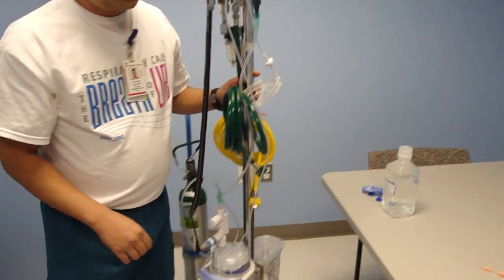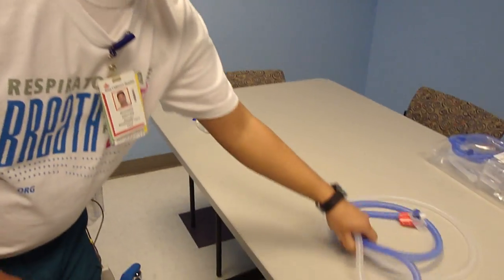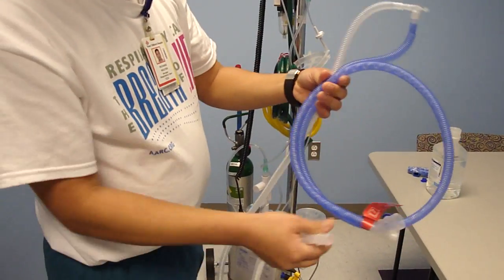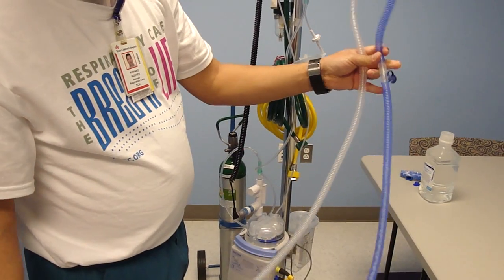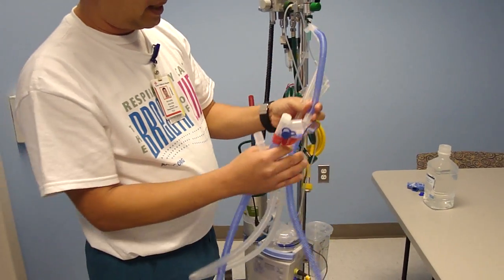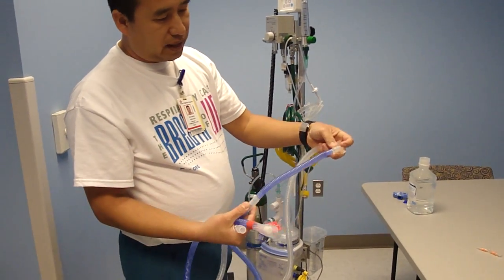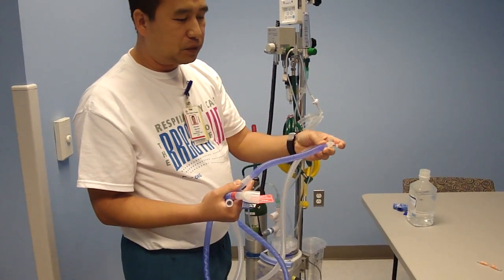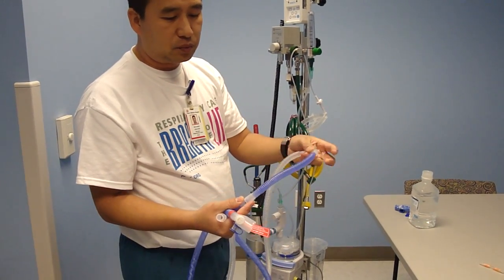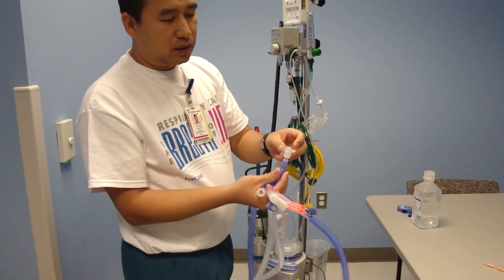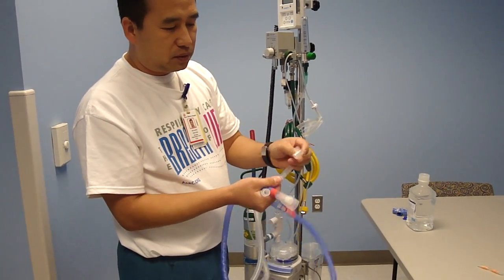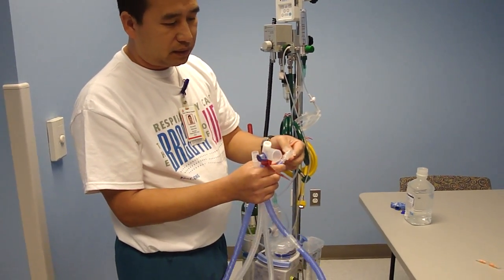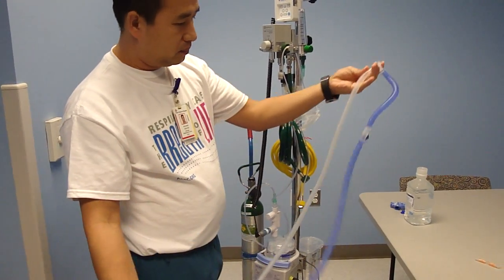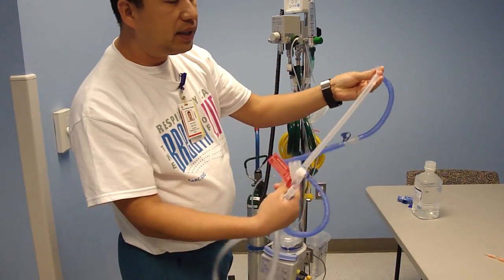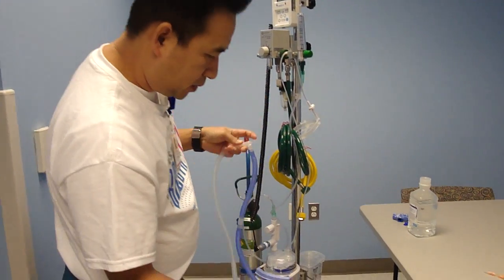Okay, and then here's our circuit. Our circuit has the blue limb as heated wire, with a very short 8 inches non-heated, so you're going to expect some condensation buildup. That's pretty normal. They come with a little elbow adapter for leak testing the circuit, and your expiratory limb is non-heated.